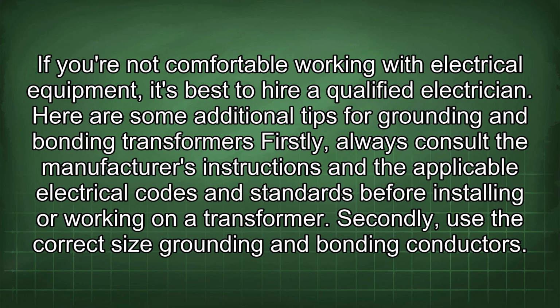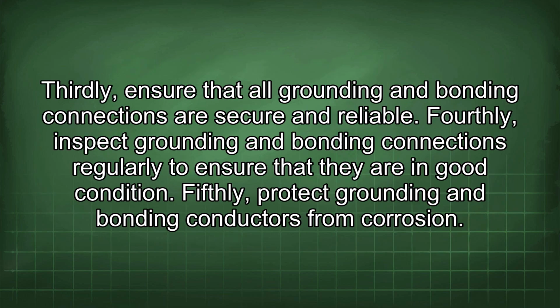Here are some additional tips for grounding and bonding transformers. Firstly, always consult the manufacturer's instructions and the applicable electrical codes and standards before installing or working on a transformer. Secondly, use the correct size grounding and bonding conductors. Thirdly, ensure that all grounding and bonding connections are secure and reliable. Fourthly, inspect grounding and bonding connections regularly to ensure that they are in good condition. Fifthly, protect grounding and bonding conductors from corrosion.